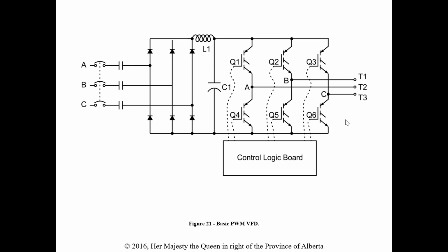UPS. So then it talks about your basic pulse width modulation. So it's showing us our circuit. This microprocessor provides the control logic that controls the switching. Both the microprocessor in the control logic board and the method of programming the control circuit produce the required output, and may be different between manufacturers. So again, this is the control logic that's basically telling these guys when to switch, how long to stay on, depending on whatever output we need. Okay, so again, that's happening very, very fast. That's why we're using solid state switching.